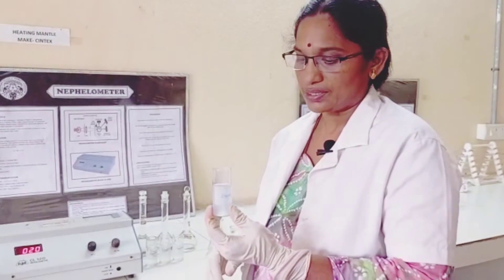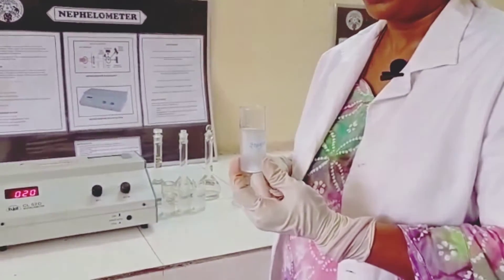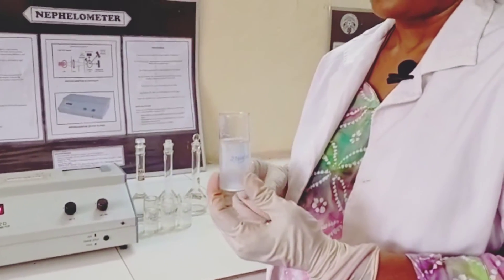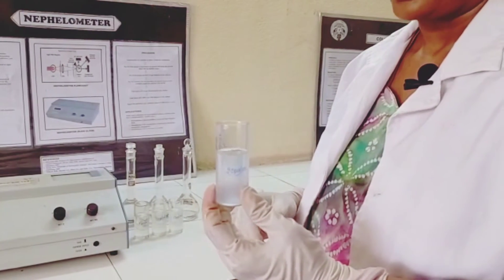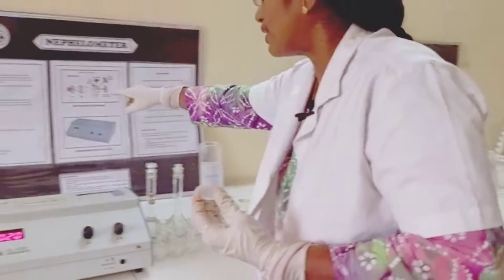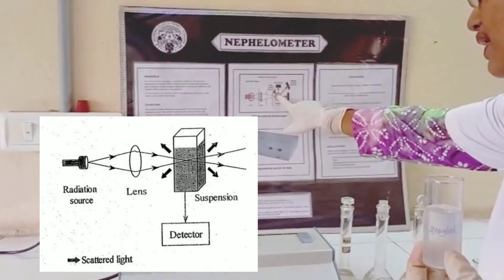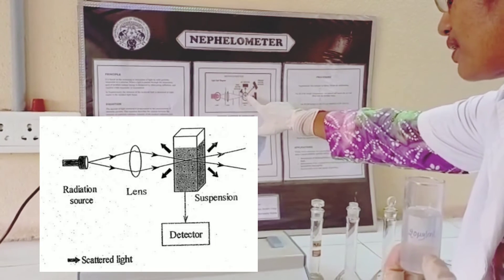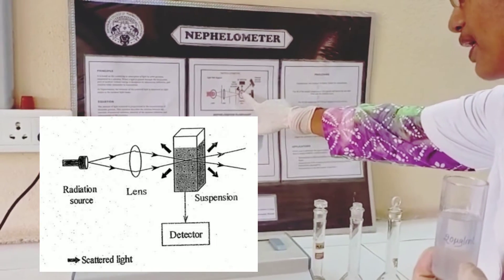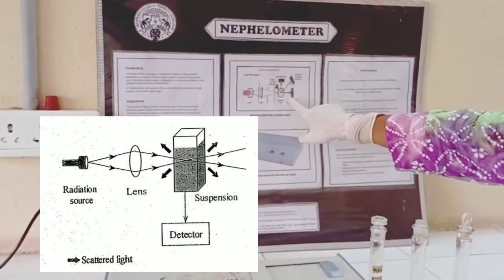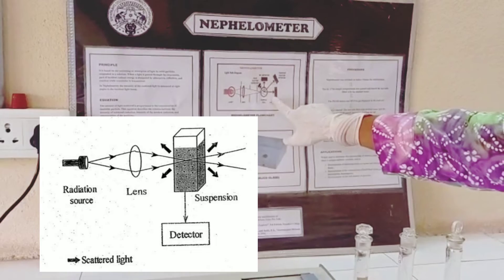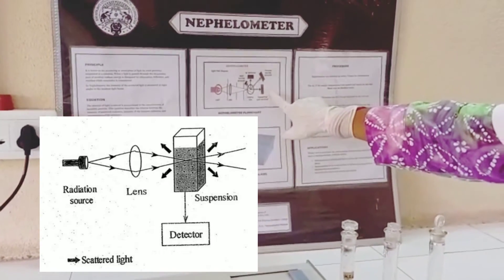The principle involved in nephelometry is measurement of the intensity of the scattered light. Here is a barium sulphate suspension — when light passes through this barium sulphate solution, the light gets scattered in all directions. You can see when light passes through the solution it gets scattered in different directions, and the scattered light is collected and measured at certain angles. We get the scattered intensity readings in the form of NTU, that is nephelometric turbidity units.